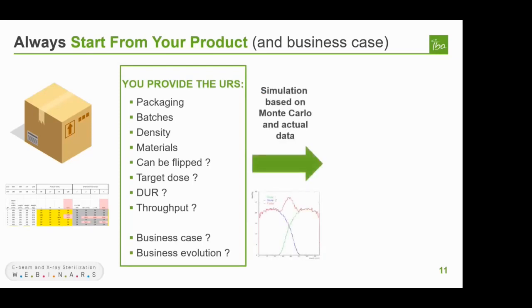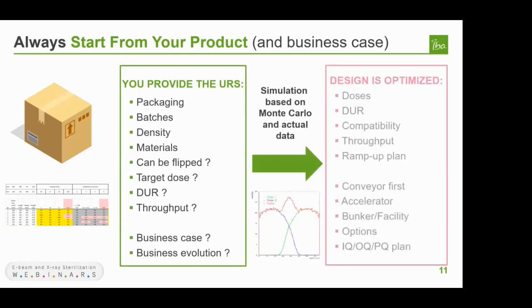After the URS is in place, Monte Carlo simulations are performed to determine a number of configuration requirements, like beam energy and a decision on the necessity of two-sided treatment. Next, the rest of the design is optimized for product dose requirements and production volume. The configuration design begins with conveyor selection. With that in place, other options can be selected for the integrated solution to meet the user requirements. Finally, a plan is generated for installation, operation, and product qualification, IQ, OQ, and PQ.